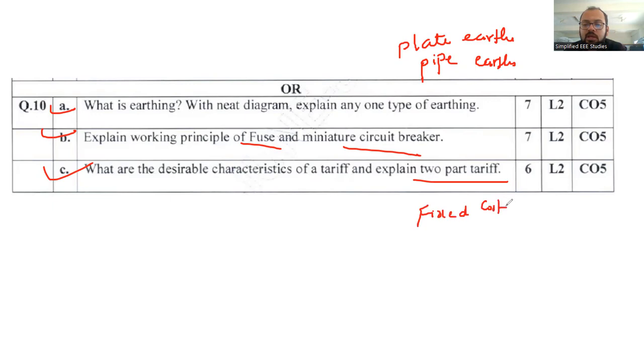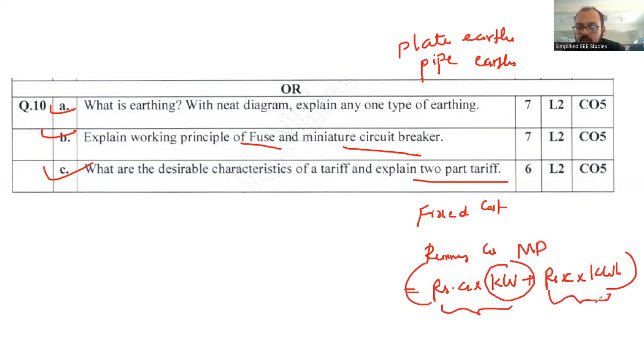Two-part tariff has two components: one is fixed cost and the other is running cost. Rupees A into kilowatts plus Rupees C into kilowatt-hour. Fixed cost depends on maximum demand, while running cost depends on the number of units consumed.